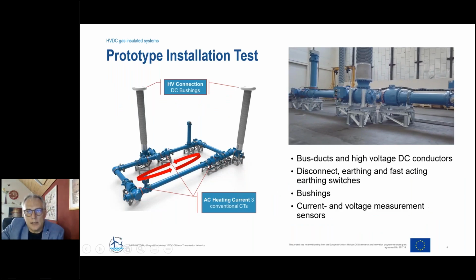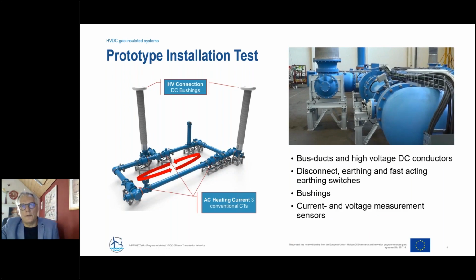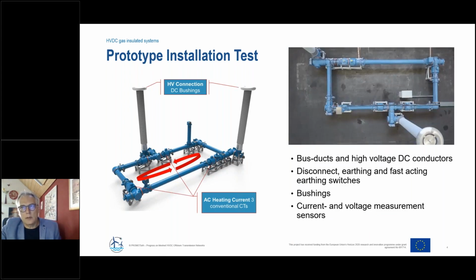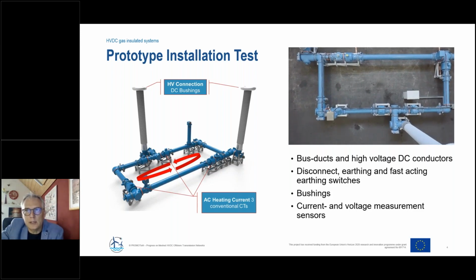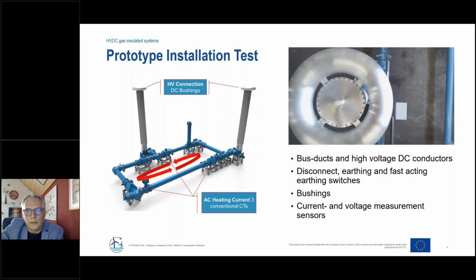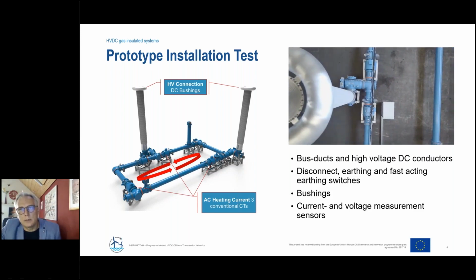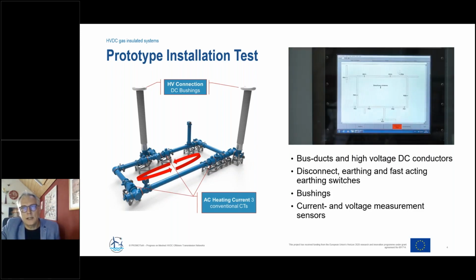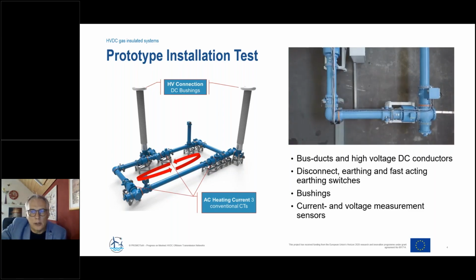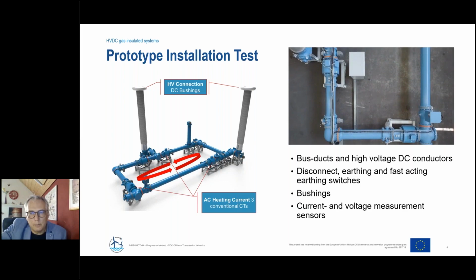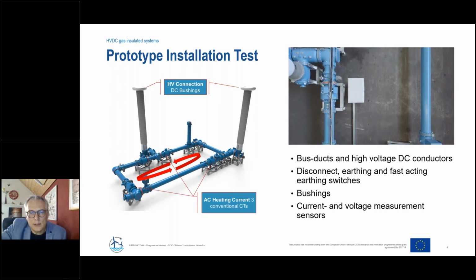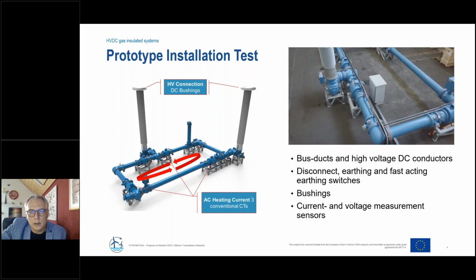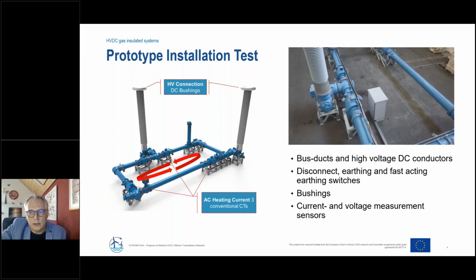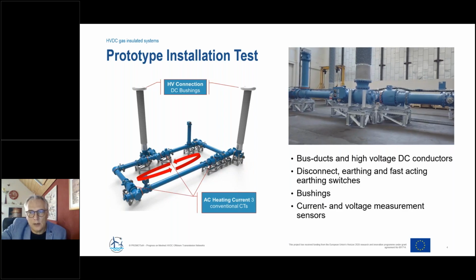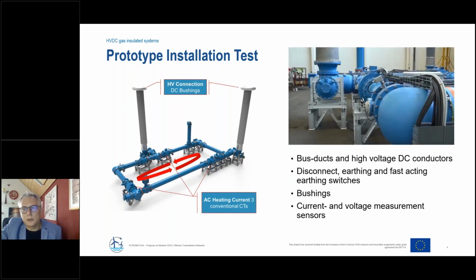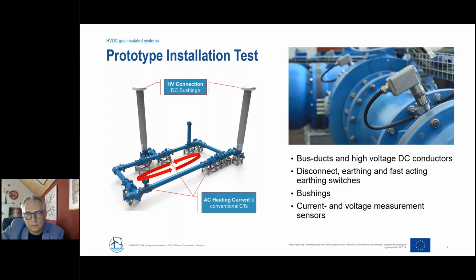Some more words about the installation itself. Of course, there was a request or a demand from users, from utilities, from regulators to perform a long-term test, a so-called demonstration test or prototype installation test. To perform that, we have prepared a test setup which contains all typical GIS components like bus ducts, high voltage DC conductors, disconnectors, earthing switches, fast acting earthing switches, bushings, and current and voltage measurement sensors.